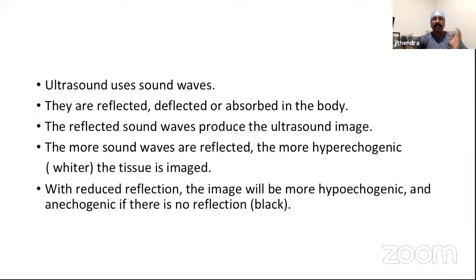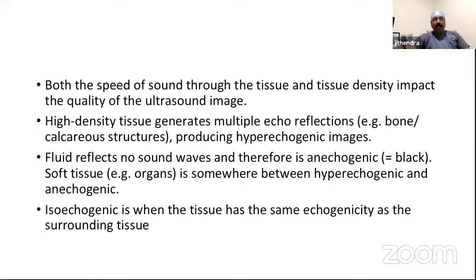While passing through tissue, the waves are either reflected, deflected, or absorbed in the body. The reflected waves that come back to the transducer produce the ultrasound image. The more the sound waves are reflected, the more hyperechogenic, that is whiter, the tissue appears in the image. With reduced reflection, the image will be more hypoechogenic, or anechogenic if there is no reflection, which appears as a black image. We need to know that both the speed of sound through the tissue and tissue density impact the quality of the ultrasound image. High density tissue generally generates multiple echo reflections, for example bone or calcareous structures, which produce hyperechogenic images. We'll see slides on that later.